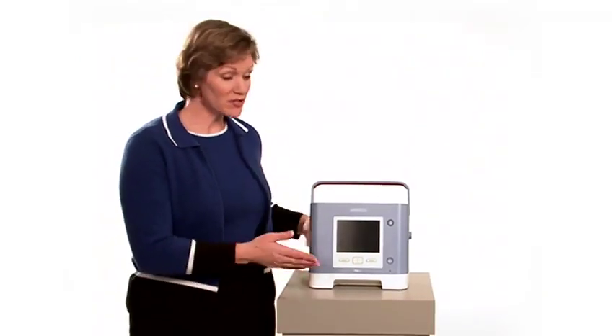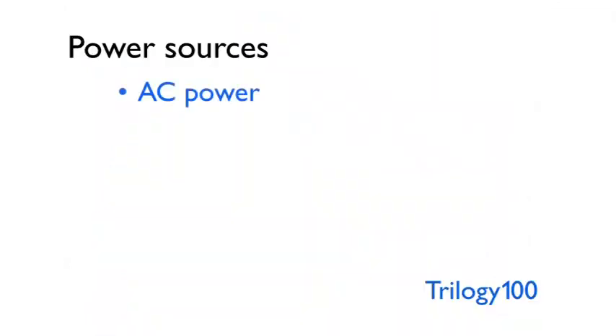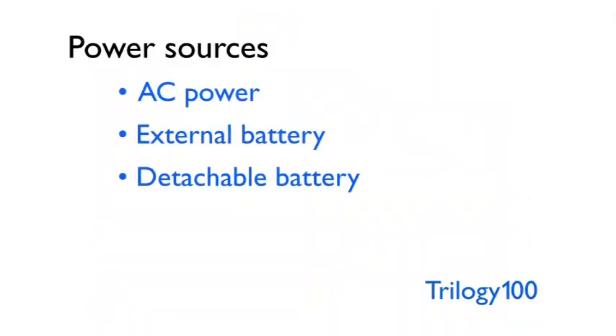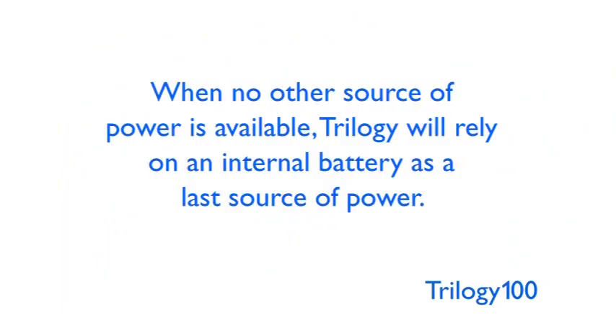Once Trilogy 100 is on a solid surface, you can start the setup by providing power. Trilogy can be powered by 4 different sources: AC power, an external battery, a detachable battery pack, and an internal battery. The device will always use AC power if available. When AC is not available, it will run on its external battery if connected. If the external battery loses its charge, Trilogy will run from the detachable battery pack. When no other power source is available, Trilogy will rely on its internal battery as a last source of power.